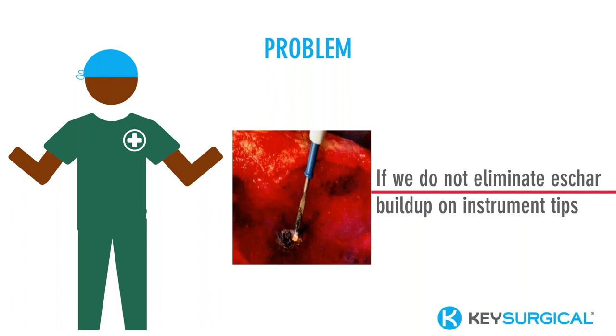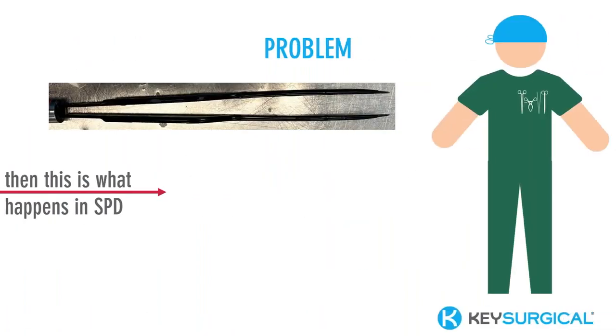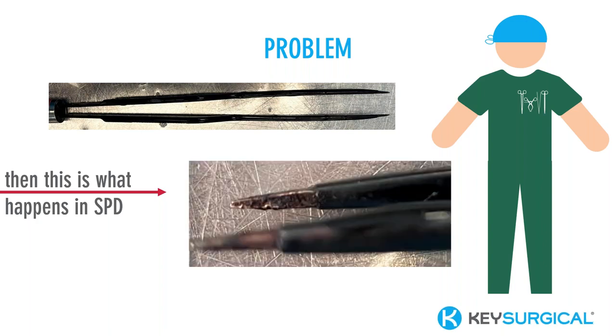So the first one that we'll talk about today is just in the operating room. If we do not eliminate eschar buildup on electrosurgical instrument tips, well, eschar buildup can significantly slow down the manual cleaning process. As you can see here, these are bipolar forceps that I received in the decontamination area that were not cleaned off during the procedure. Getting this off often happens with the metal brush, which we know can be an issue for this instrument, and it can be extremely hard to do. It often equals longer soaking times and constant inspection of whether it is actually cleaned, in air quotes. In a few slides, we'll discuss how significant this time strain can really be in sterile processing. You need a lot of elbow grease for these when they come down with nice buildup.